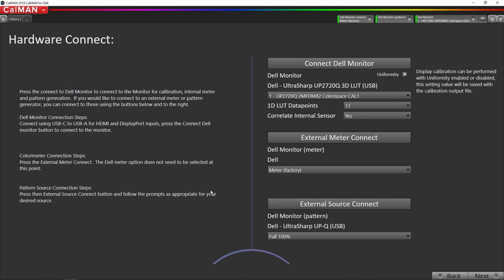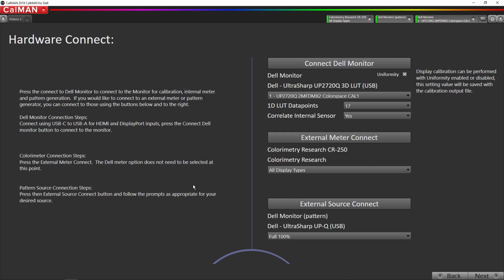Okay. Now we're going to connect to our external meter, which is our Colorimetry Research CR-250 reference spectroradiometer. So we're going to use that to profile the internal meter or correlate the internal meter. So then the internal meter reads like the spectroradiometer. So I'm going to click this button here. And now I'm going to check this checkbox and select the correct COM port that the CR-250 is connected to. Okay, so we have everything connected, so we're going to go to next.